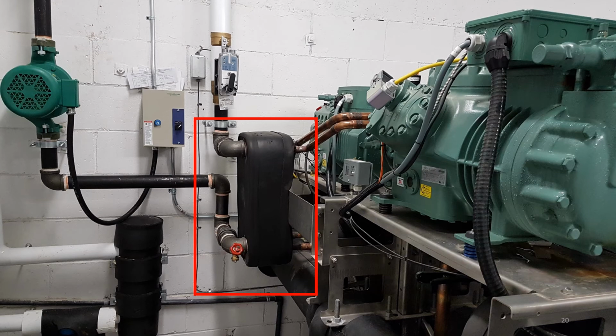In terms of controls, the hybrid system is very simple. The chiller controls the chilled water load like any other chiller. The heat recovery chiller has a temp sensor in the boiler loop. When the temperature drops below set point, the chiller begins to modulate hot refrigerant to the auxiliary condenser and starts the circulation pump to reject the heat to the boiler loop. Essentially, it acts like another boiler.